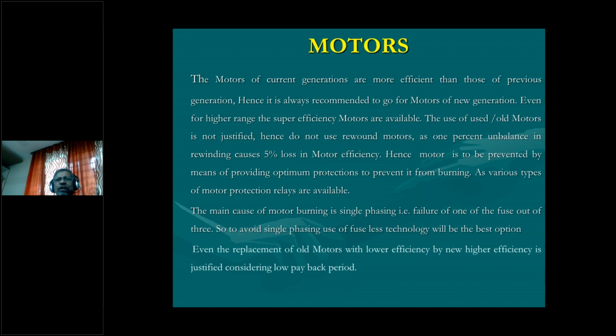Even the replacement of old, lower efficiency motors with new higher efficiency ones is justified considering the low payback period. I'll give an example of a 150 HP motor, that is 110 kW. The efficiency we worked out was very low, around 67%. The new motor of 110 kW comes to nearly 95%. Considering the payback period, in a continuously running industry, it was less than 5 months. So friends, there is a huge business in old motor replacement. That is why I mentioned that replacement of old motors with lower efficiency by new higher efficiency ones is justified considering the low payback period.